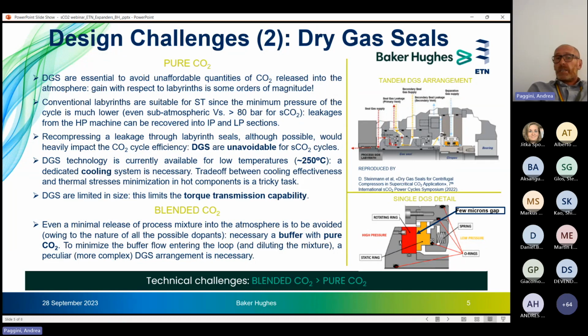The problem is that the current dry gas seal technology is limited in temperature. We are saying the maximum temperature is around 250 degrees C. Dry gas seal suppliers are working a lot to push up the temperature limitations, but as a matter of fact, at least in the short to medium term, no viable option other than dry gas seal cooling exists. So it should be somehow intuitive that finding an optimal compromise between conflicting requirements like cooling effectiveness, cooling flow minimization, and limitation of the thermal stresses induced in the hot components is a tricky task. Probably this was the thermal management challenge in the slide question that was answered by some of the people. In this sense, it's definitely a correct answer.